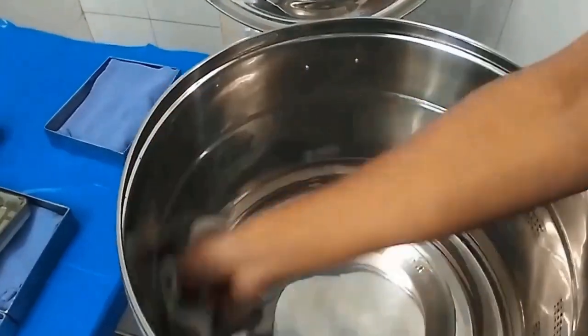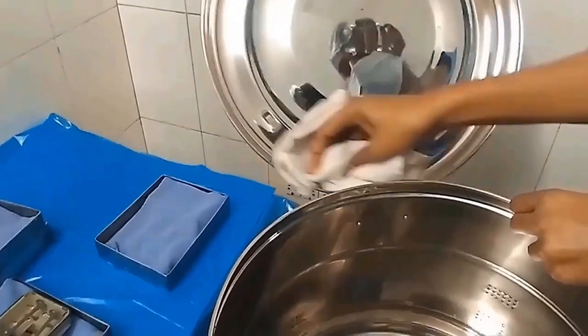Then comes bin packing. Before bin packing, thoroughly clean the bin first, then keep the class 1 indicator over the towel, then keep the trays in a perpendicular alignment, that is in opposite direction. Keep the class 1 indicator in top, middle and bottom of the bin. Don't do tight packing. Loose packing only allows the steam to spread inside the instruments.